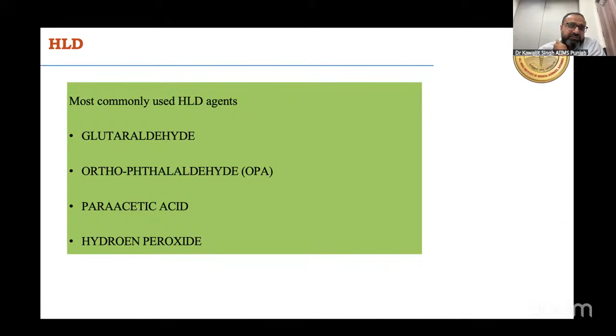I have described the four most commonly used agents. First is Cidex, we all know, glutaraldehyde. Second is OPA. Third is peracetic acid, and then hydrogen peroxide. Glutaraldehyde is a 2.4 to 2.5% solution. In the market, it is available under the name of Cidex. It is the oldest used and the gold standard HLD chemical, and it is usually available in an inactive form and requires mixing and activation before it is used, and it is reusable up to 14 days, and its distinct pungent odor requires a well ventilated area where we need to activate it, and the common contact time for this agent is 20 minutes at 20 degrees Celsius.